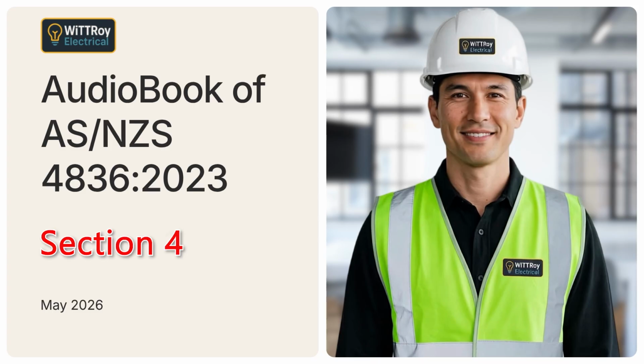Old equipment must not be assumed safe just because it looks abandoned. A disconnected-looking cable may still be live. An old switchboard may still have a hidden supply. A cable that is no longer in use may still be connected somewhere. So before removal, isolate and test.